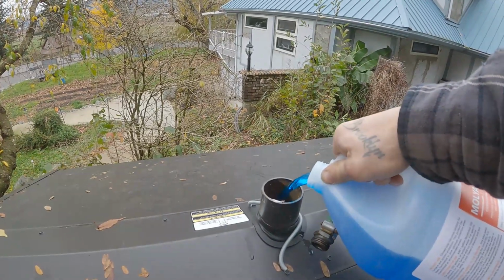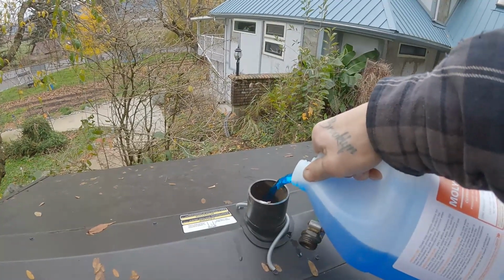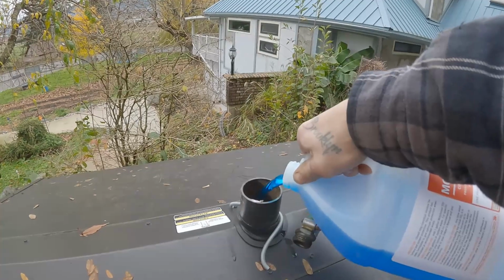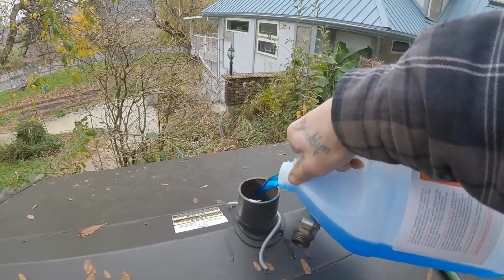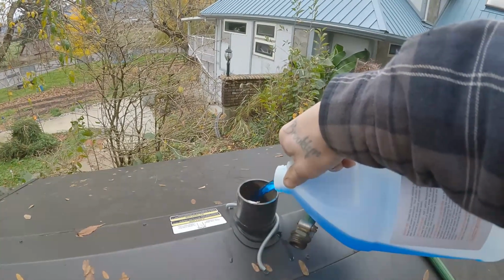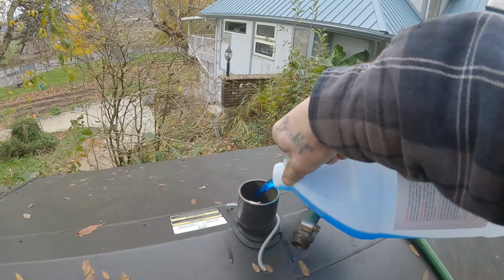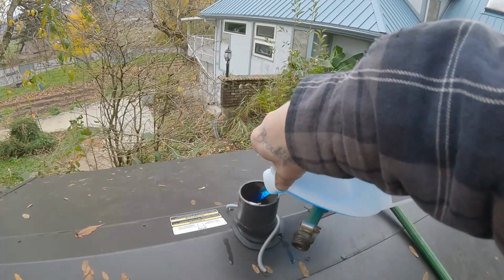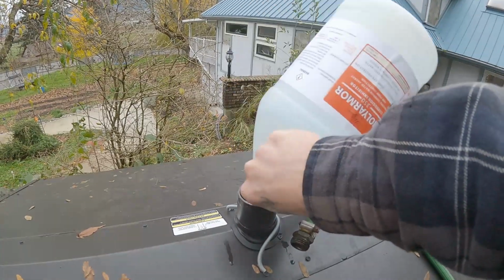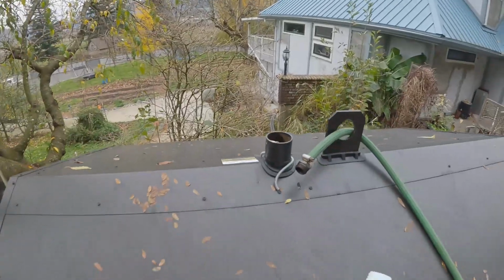Depending on if you have a big system inside, like radiant floor heat, you'd need to add more than the 3 gallons for a Clean Fire 900. Since we're just running 1 line in, straight to the furnace and then the heat exchanger, it's a short line, so all we need is the 3 gallons. But when we get this up country, since our system is so long, we'll probably need to add a couple more. I should also mention we're not using just any regular water — we've tested it beforehand. This is coming from our house, and it's the correct pH, which they want between 6.5 and 8.